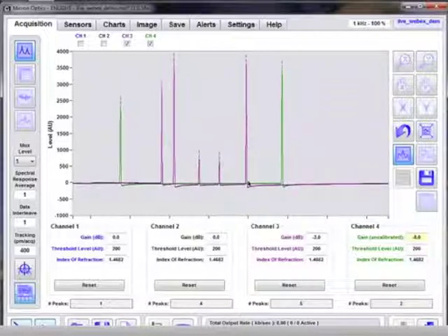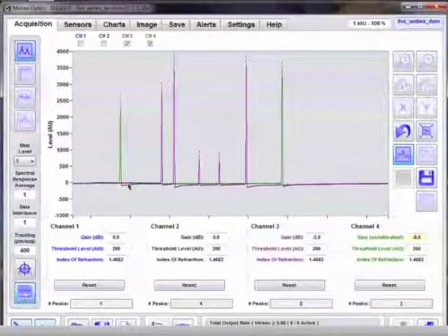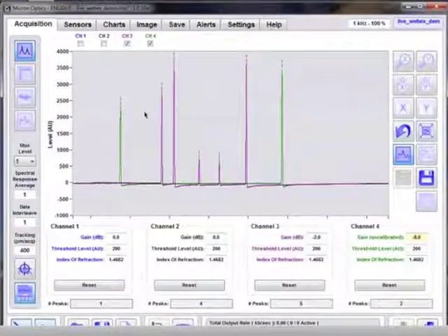That's different in an SM125. In an SM125, the full spectrum data is actually the source of the data coming from the interrogator, and peak detection is performed in the application in ENLIGHT. So in the case of an SM125, the spectral response averaging is the first place in which averaging will affect the stability and time response of the measurement.